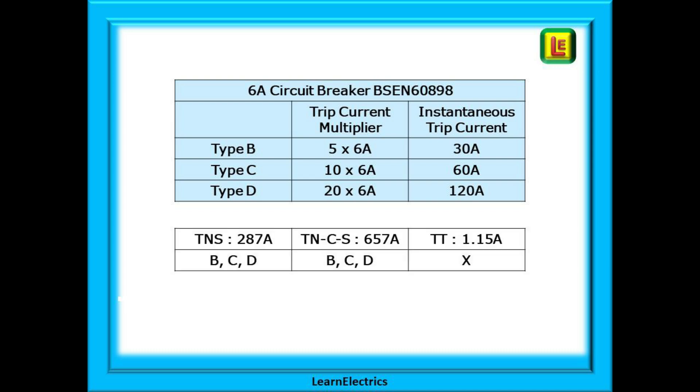What does this mean for each of the earthing systems? For a TNS system enough fault current will flow through a 6 amp breaker to operate a type B or C or D breaker within the required time for safety. For TNCS the same is also true. The 6 amp MCB will trip safely for types B, C and D. But a TT system does not have a big enough fault current to cause operation of any circuit breaker. And this is one reason that RCD devices are always installed as additional protection in TT systems. But this is discussed in detail in another video.